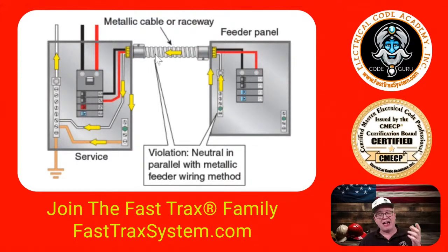But this is not. This is not an MC. This is not an AC cable because typically AC cables wouldn't be in larger than 1 gauge, so we would limit the size, okay? But it may be an AC cable if this was a smaller size remote distribution panel.